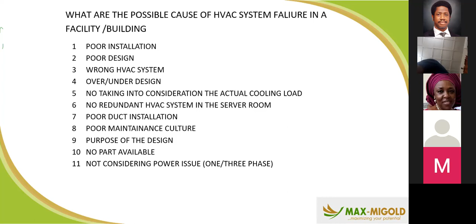So you now determine the kind of AC you want to design for. That 2 kilowatts, you cannot just divide it in two. If you know the place is very big, you cannot decide to go to the market and buy two 1 kilowatt units to install in the place. The essence is that you want everybody within that space to benefit from the cooling. So distribution also might be a factor while you are selecting.